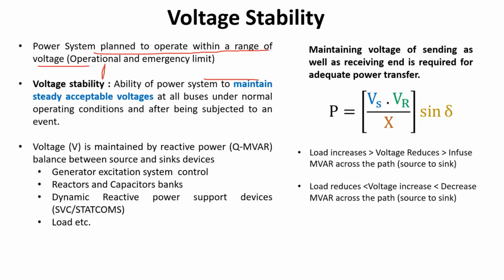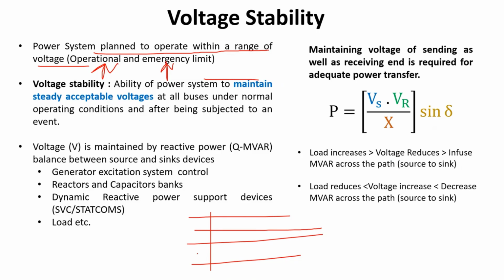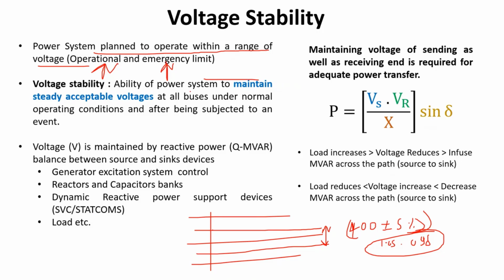So you have two real limits: operational limits and emergency limits. The emergency limit is for human safety and equipment safety, and the operational limit is what you maintain because there is a continuous rating for any equipment. It is not that any equipment is rated to operate at 400 only, one per unit. It is rated to operate within a band of range, plus minus 5%, let us say. So this is my operational range, in which, let us say, 1.05 to 0.95. This is the range in which I have to operate the equipment. So this is my operational limit.